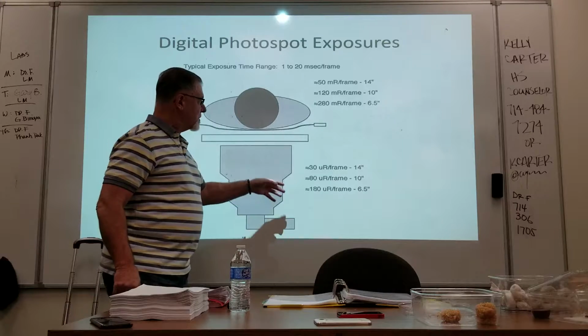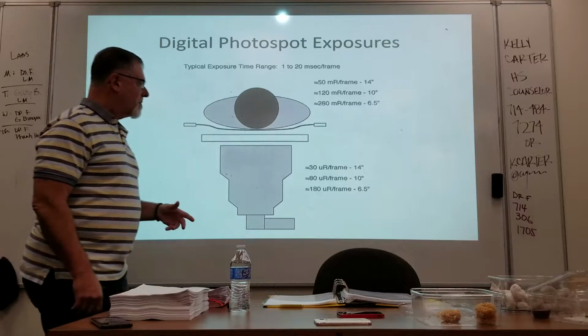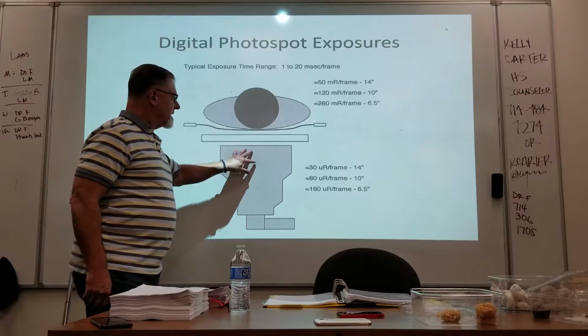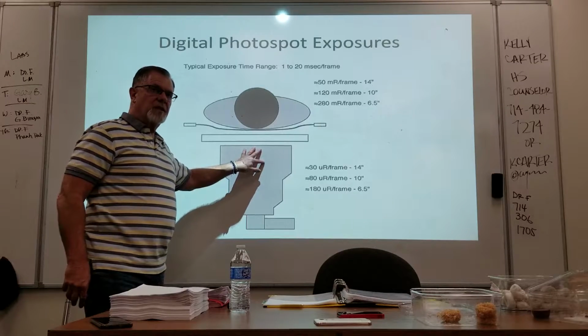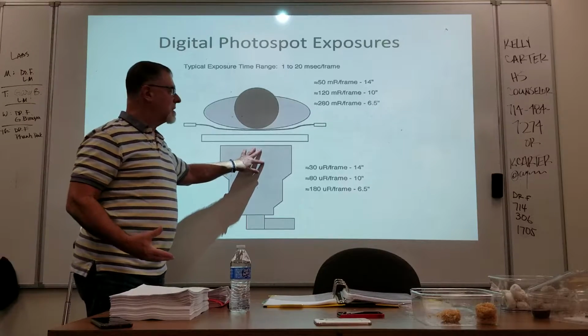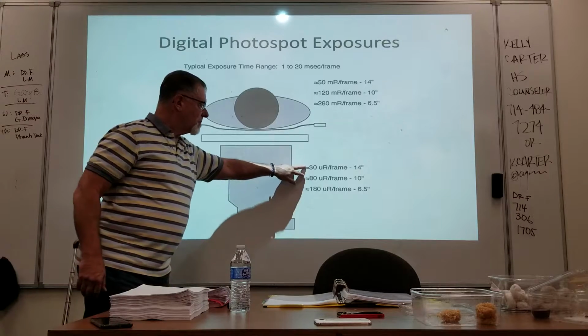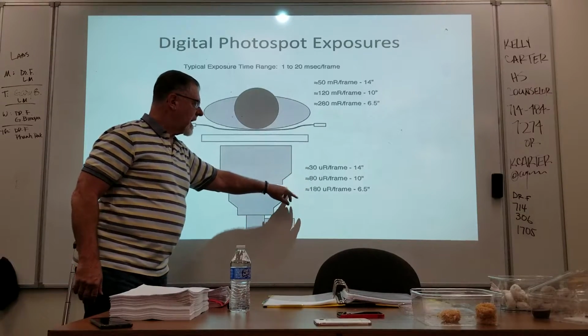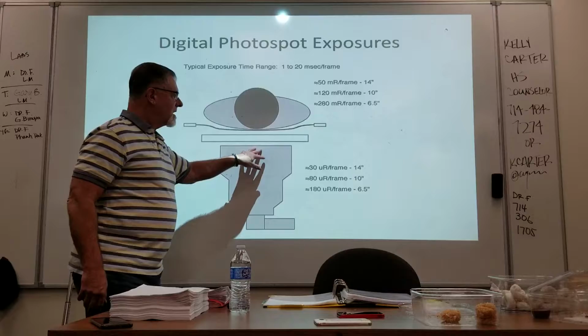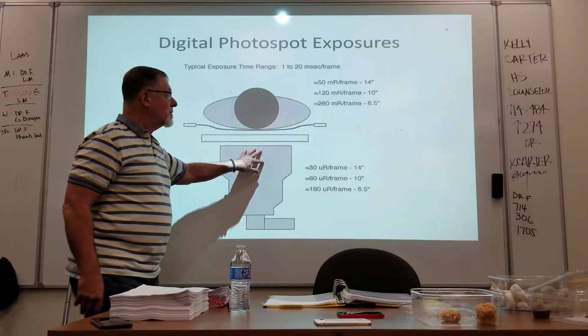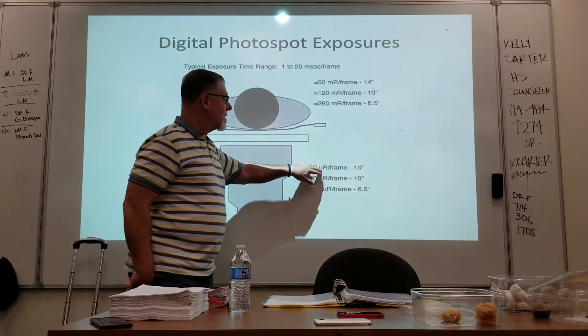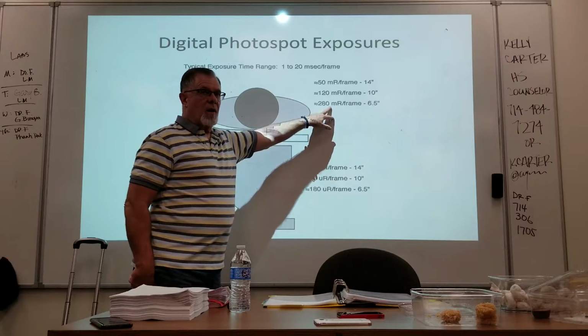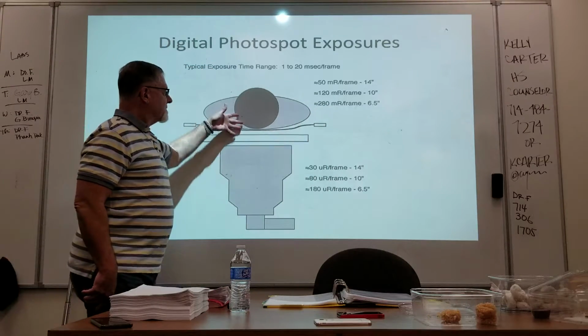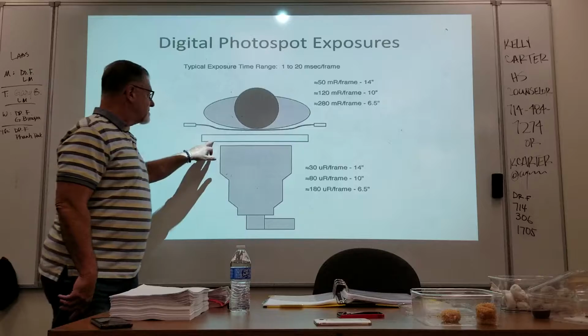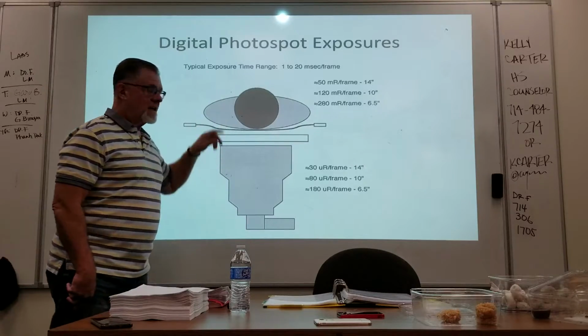For this particular unit that I used, 30 micro-R per frame is what you needed at the surface of the image intensifier to give an acceptable image. So that went from 30 to 80 to 180. So taking what was needed here, that translates to, notice you're going from micro-R now to MR. This is what the patient gets, because you have to take into account table and attenuation of the patient.